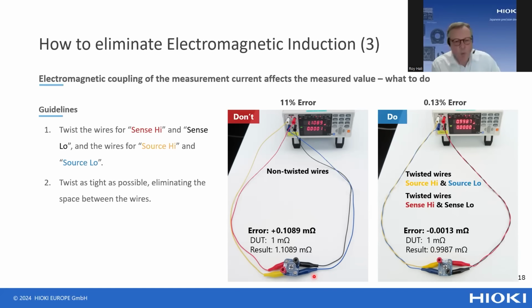In the first test, we connected the resistor just with wires with no twisting. In the yellow source-high wire, the AC current flows, causing electromagnetic flux, which is picked up by the sense-plus wire, the red one, inducing a voltage. The same thing happens on the other side. So there's a whole area where the magnetic flux is picked up by the sense wires, inducing a voltage and making the measurement inaccurate. In this situation, the measurement error is 11%.